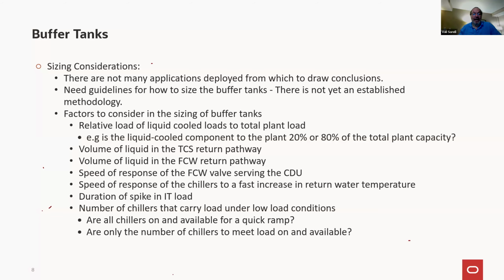Well, 5,000 gallons, that's the size of my thermal storage minus whatever resident flow I have in the piping. That's easy. That's the way thermal storage has been done. And if there's any issue that I would like to convey out to the industry, it is to think about the complexity of determining that you need a buffer tank and how big that tank needs to be. So it's a much more involved decision, even though it's a simpler device because it sits there passively.